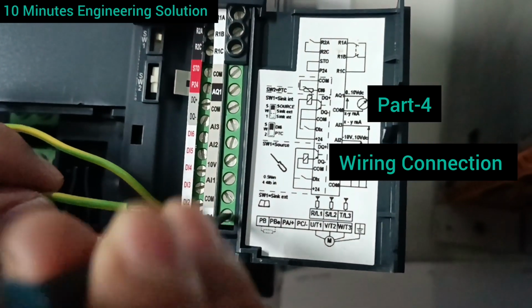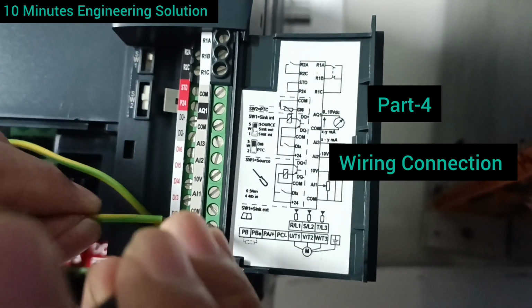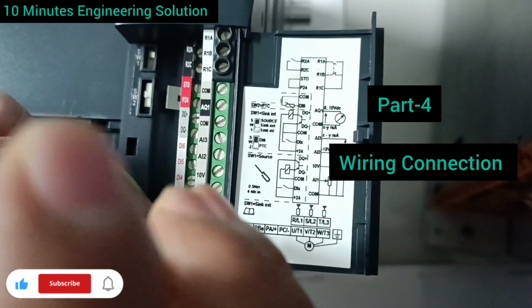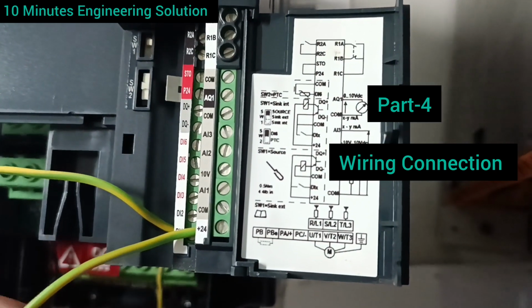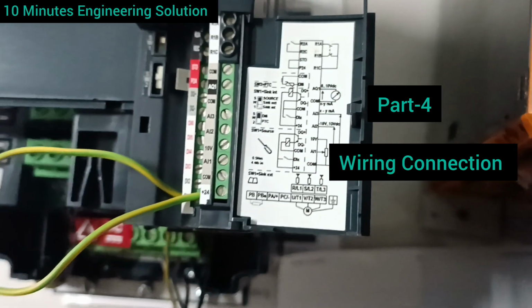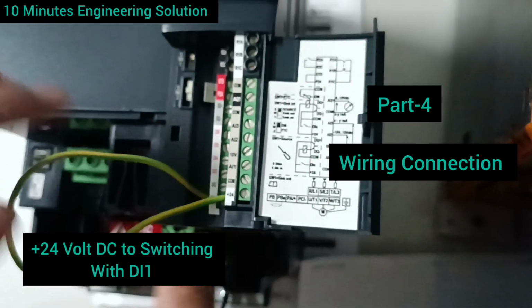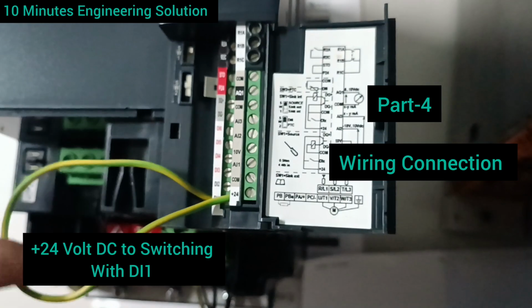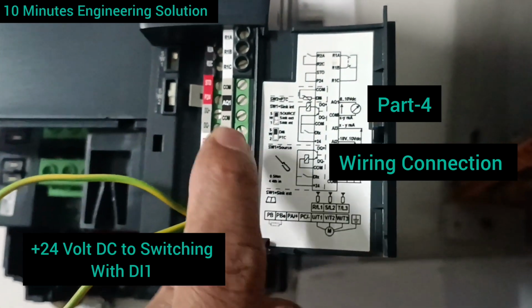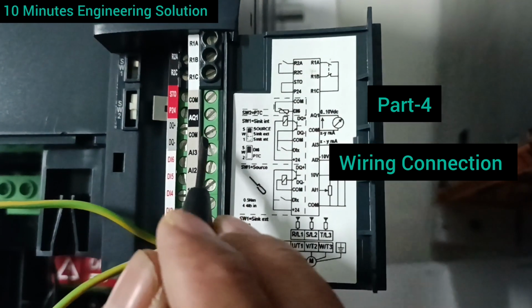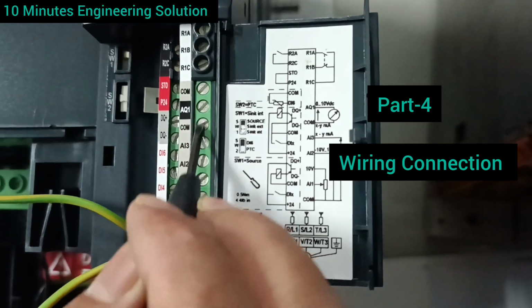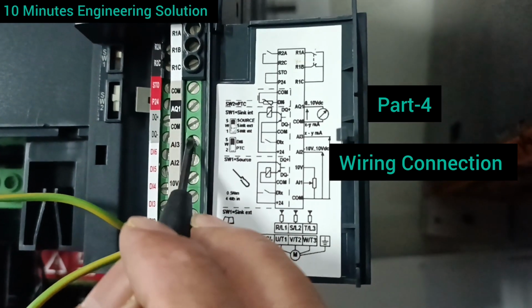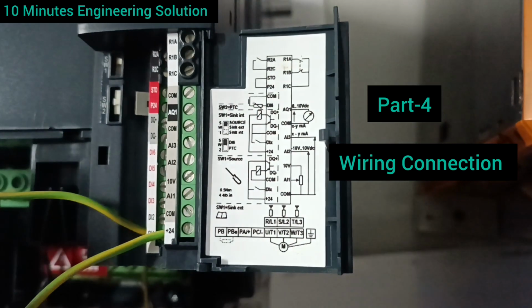But as I am making a video, I'm giving the short jumper to make the VFD ready signal. This is the jumper. In your system you can use it for a switching system. This will be the switching, otherwise the 4-20 milliampere cannot work properly. So in your system you must use the switching for DI1 and 24 volt.